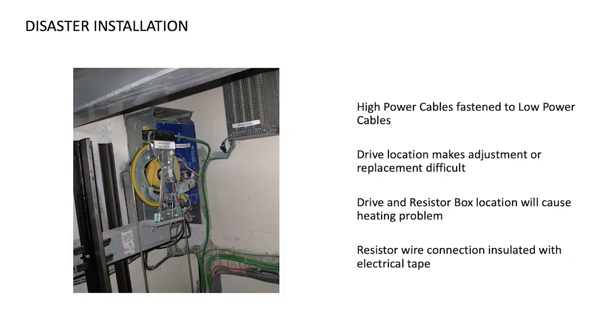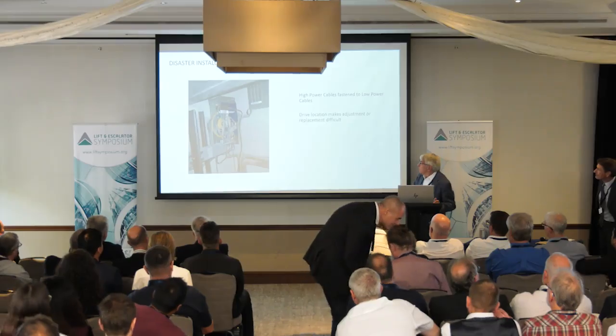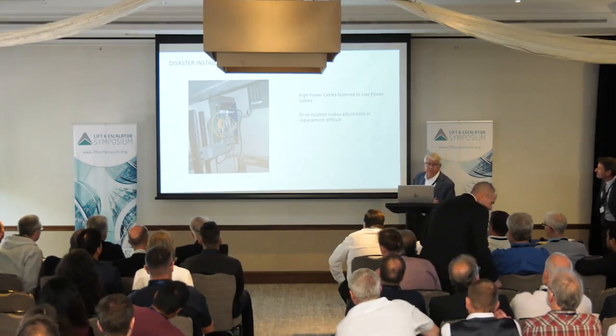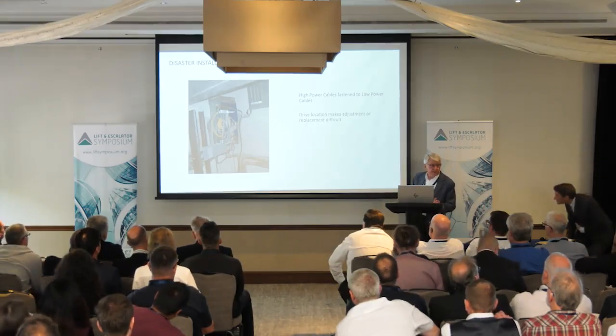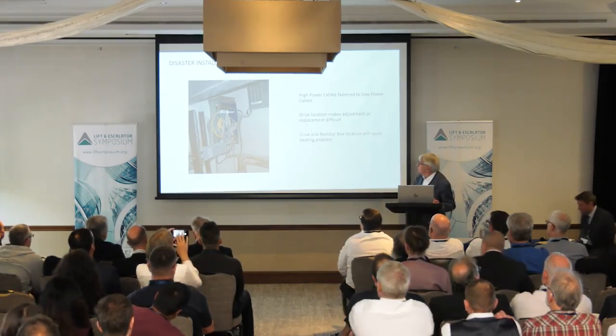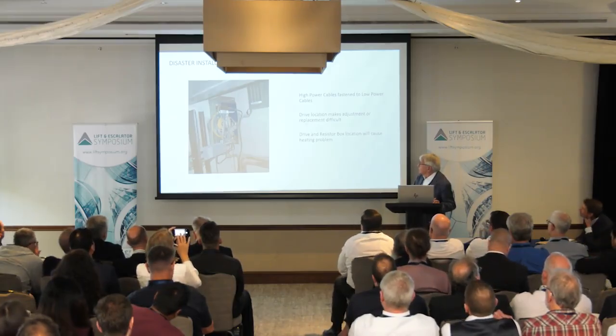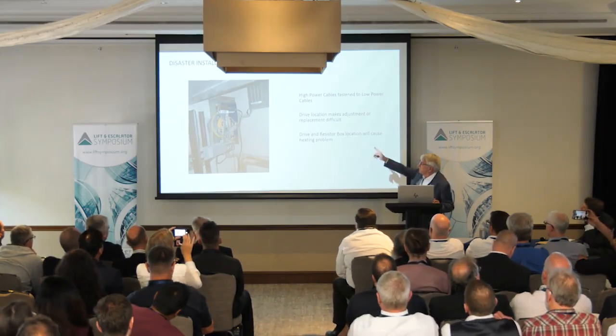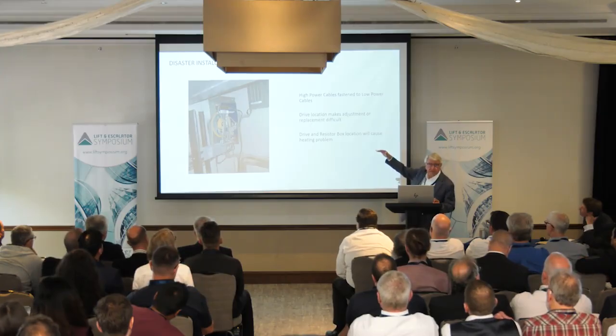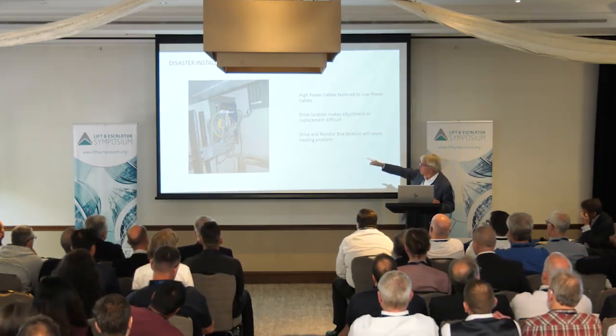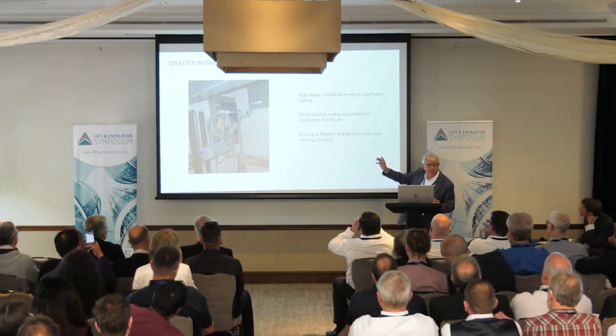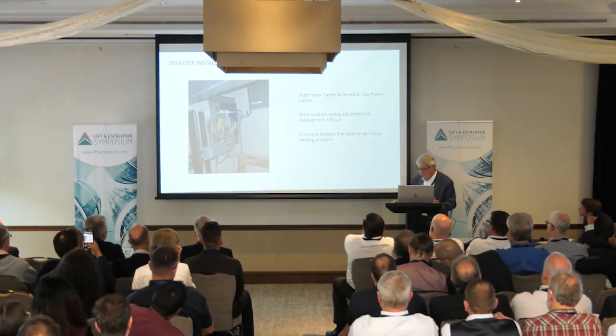Here's a real disaster. This is a variable frequency drive. The high power cables are fastened to low power cables. The drive location makes it very hard to adjust or replace, up behind the governor. And then the drive and resistor box location, these are the dynamic braking resistors, all the heat collects at the top in this machine roomless application. The heat from the drive and the heat from the resistors is bad for both. It's just a bad installation.